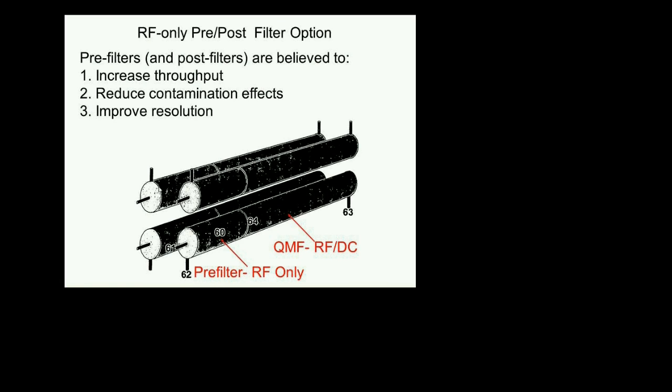There are a lot of papers out there. They're old, but they're still absolutely true from the early days of quadrupoles. A fellow called Brubaker did a lot of this work, and pre-filters work. They add complexity to the device, they add cost to the device. But if contamination, particularly by hydrocarbons, is a big problem for you, I highly recommend it. They do provide a little bit more sensitivity. They are less sensitive to contamination effects. And in general, they provide better resolution than standard quadrupoles, with the peaks being a little more narrow than what you see in a standard quadrupole assembly. Okay?